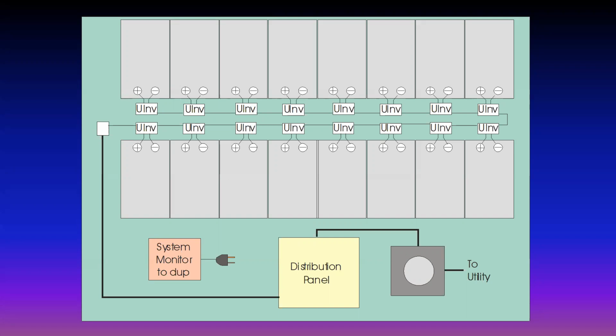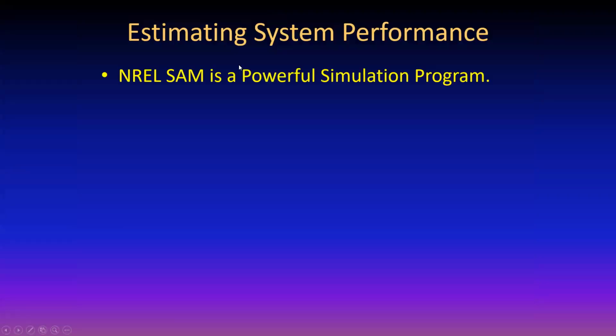And that system monitor, again, probably is going to be included in the combiner panel that combines and has communications, and then a single circuit breaker going into the distribution panel. Adds a little bit of cost, but it also adds a whole lot of reliability and the ability to monitor. All right, so how do you estimate the performance of these systems?